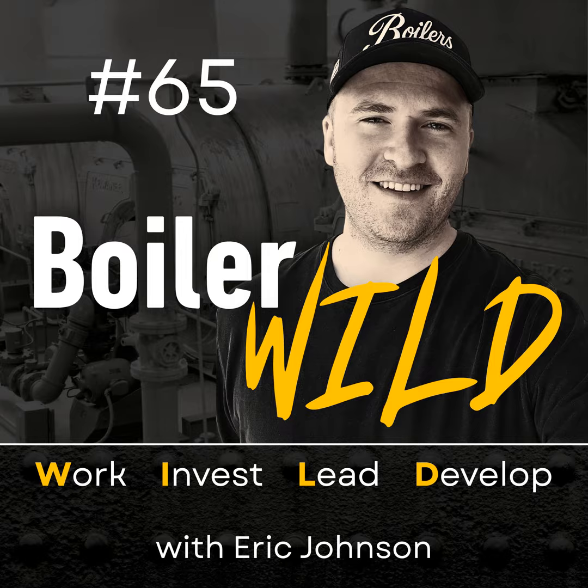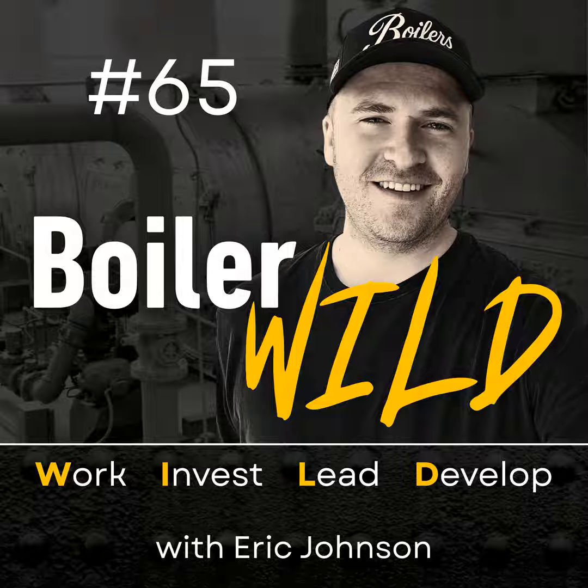Today we're going to be talking about stack temperature of a boiler. And by stack, I mean flue gas temperature and whatever else you want to call it. There are some other general names, but typically people say boiler stack temperature or flue gas temperature. Your flue gas temperature is an indicator of your boiler efficiency and its health and how it's running.